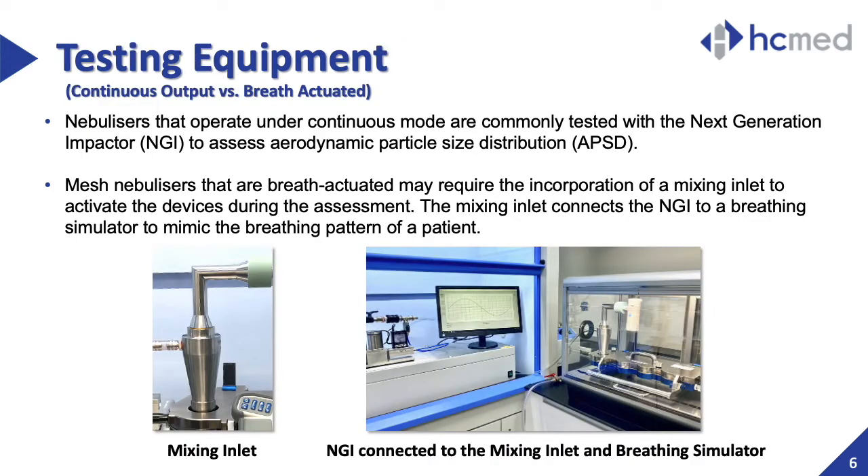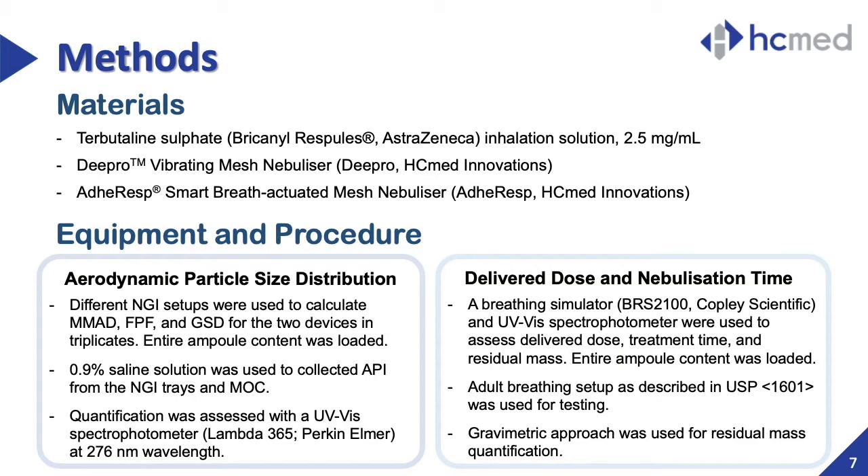As for the testing equipment, aerodynamic particle size distribution analysis is commonly performed with a next-generation impactor when testing continuous output nebulizers. However, due to the special characteristics of breath-actuation, the incorporation of a mixing inlet is required. The mixing inlet is a component that connects the next-generation impactor system to an adjacent breathing simulator, allowing to mimic breathing patterns during the testing while triggering breath-actuated functions of the mesh nebulizer. In this study, 2 mL of terbutaline sulphate solution was used for comparison tests.